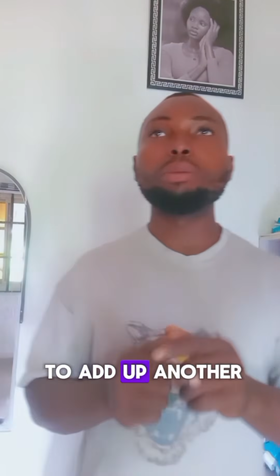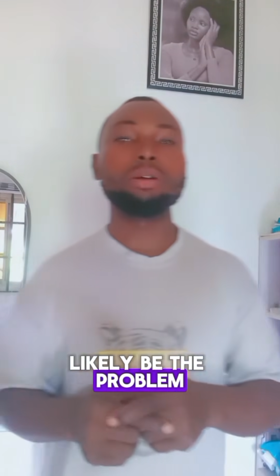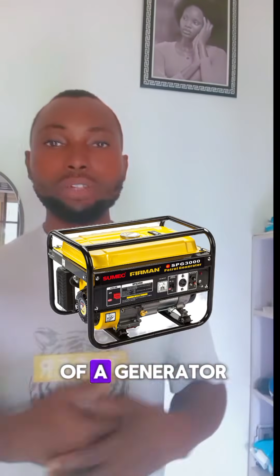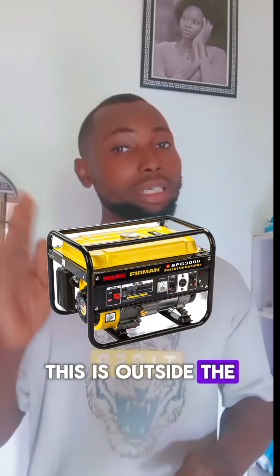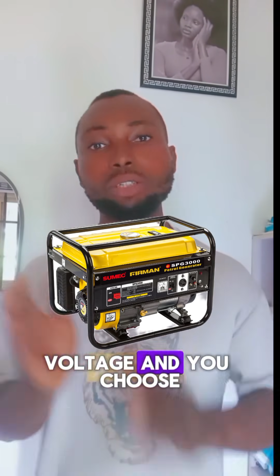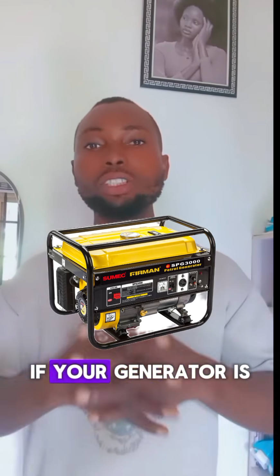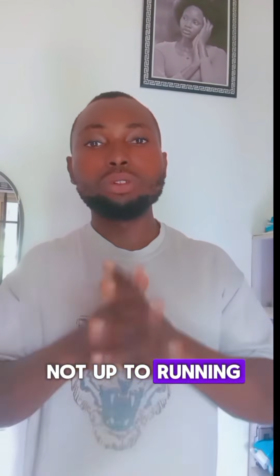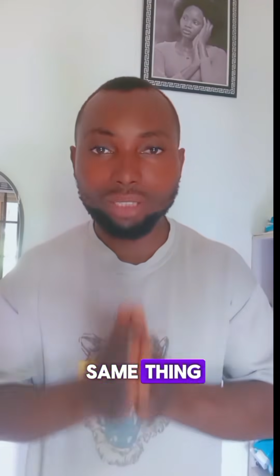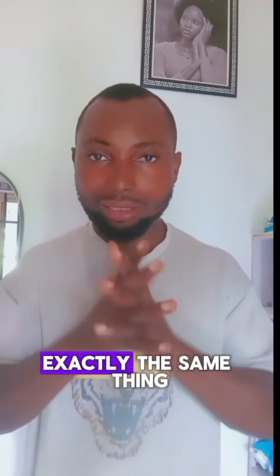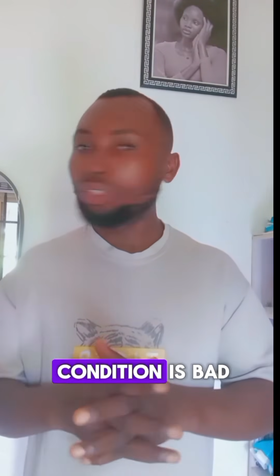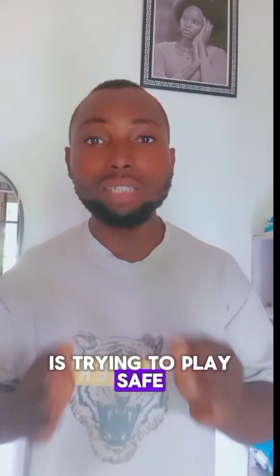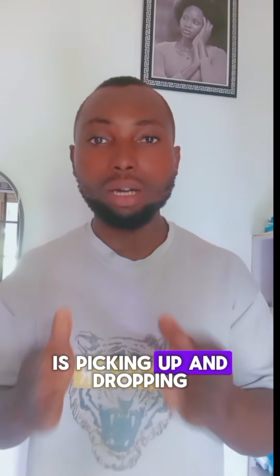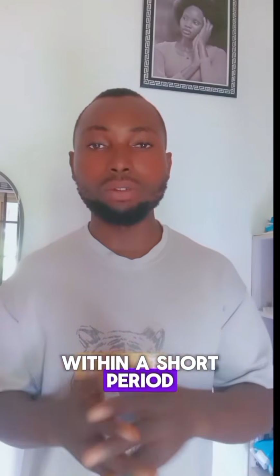Now, I want to add another thing that could likely be the problem of such an issue. I actually made mention of a generator. Understand? The generator sets. This is outside the grid now. The grid is actually giving you a low voltage and you choose to use your generator to run it. If your generator is not up to running the air conditioner, you will still experience the same thing. Not that your air conditioner is bad, no. Your air conditioner is trying to play safe. That is why it is picking up and dropping within a short period of time.